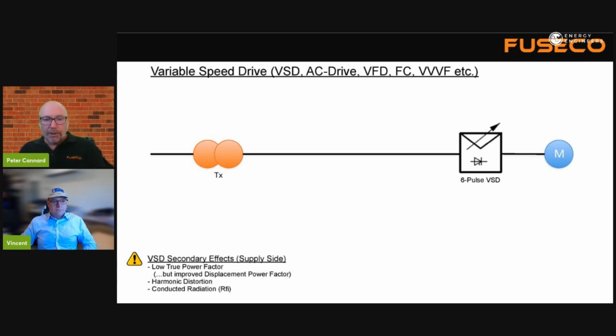I'm going to combine looking at the motor and variable speed drive. On the right-hand side, we have the motor load in the application, connected to a pump or fan and the like, and a motor controller called a 6-pulse variable speed drive. We're going to look at the secondary effects of the variable speed drive, but also talk about the motors themselves, which would be regarded as a DOL application if directly connected online.